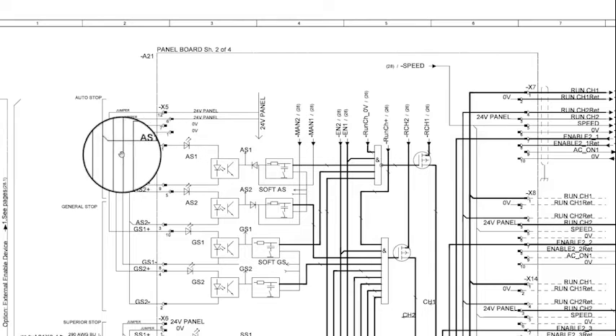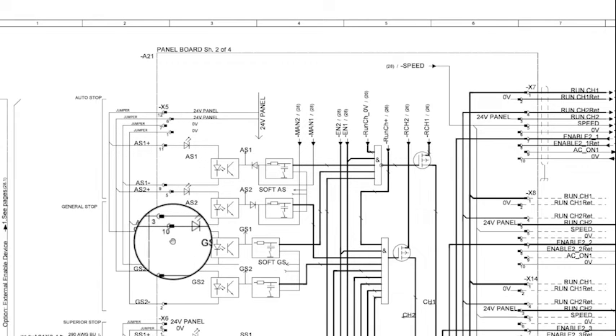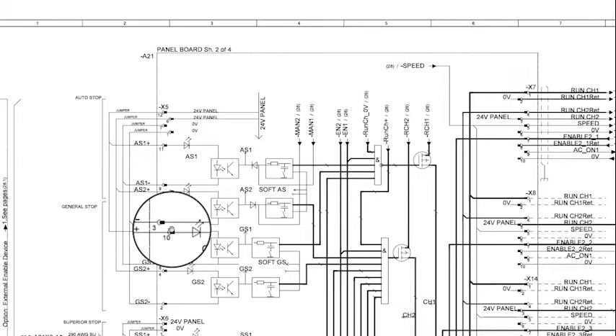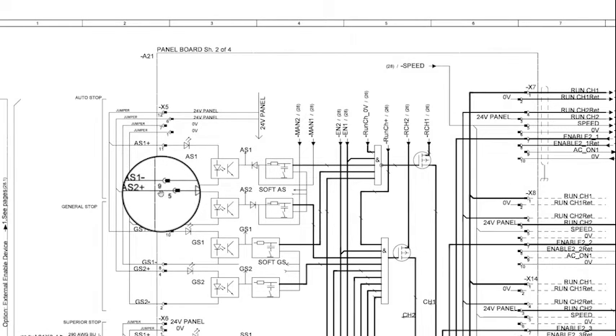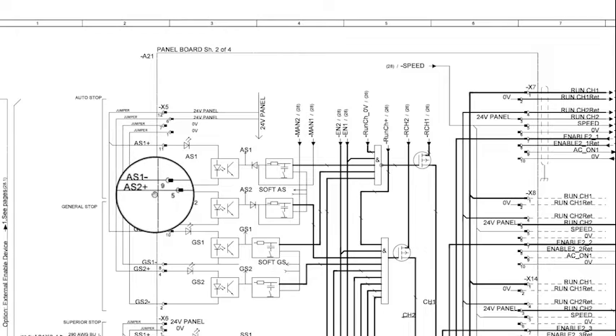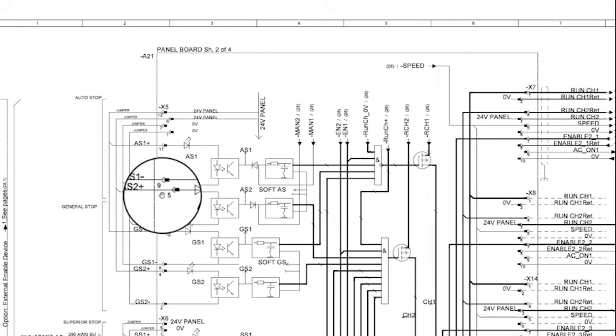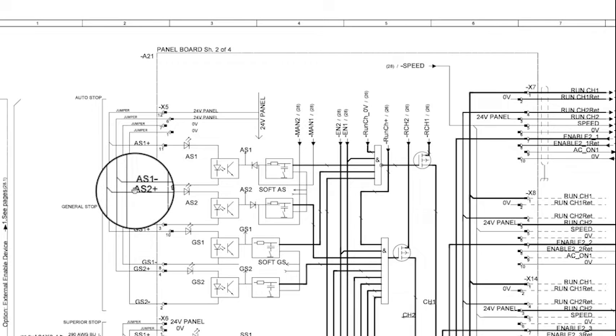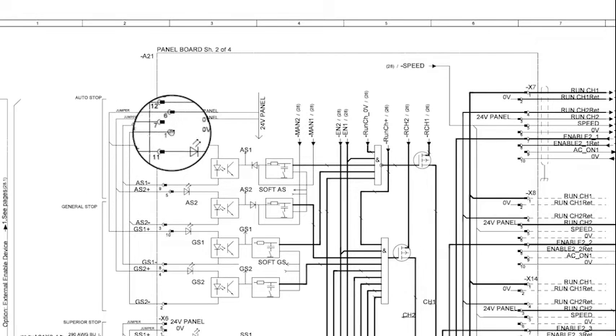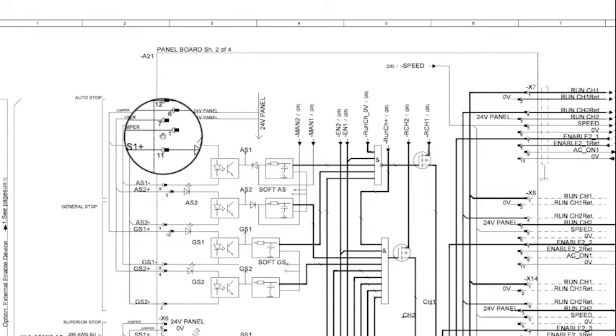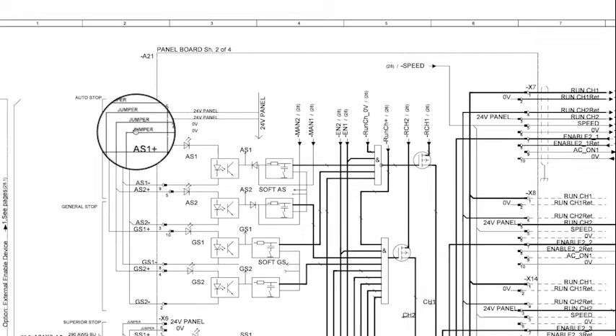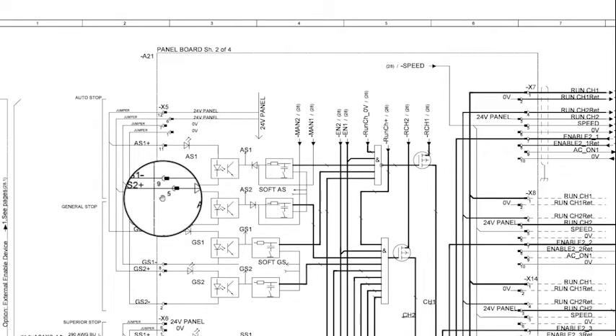Now that we know where AS1 positive gets its 24 volts from with the factory jumpers installed, let's take a closer look at AS1 negative or 0 volt and where it's located on connector X5 position 9. As you can see in the circuit diagram there is a very similar factory jumper in position 7, 8 and 9, which position 7 is the 0 volt supply from the panel board.